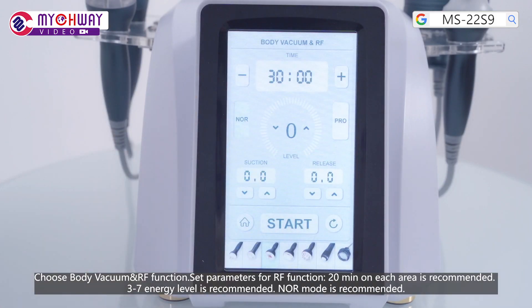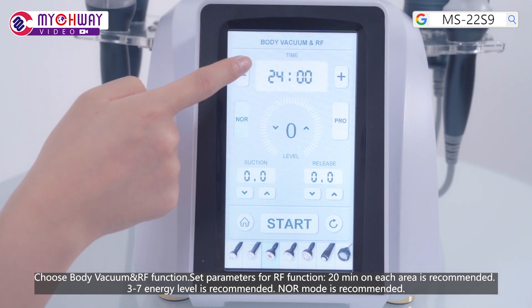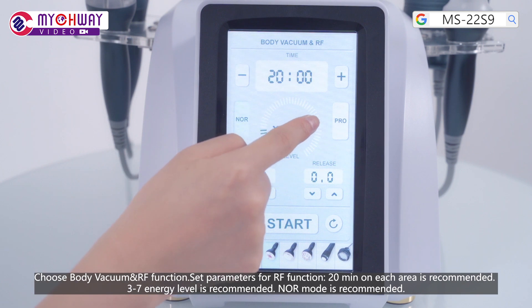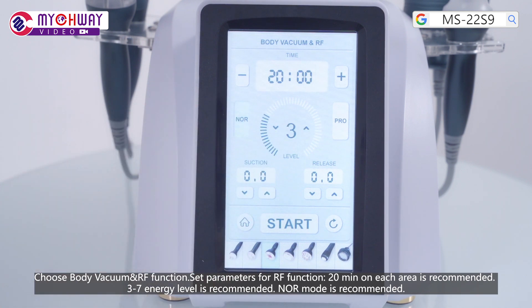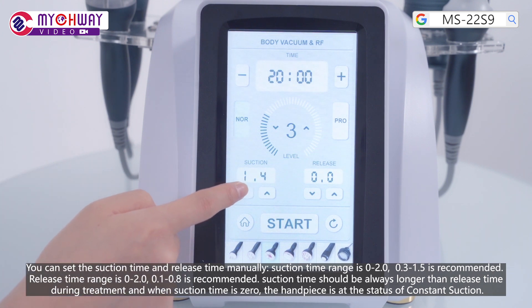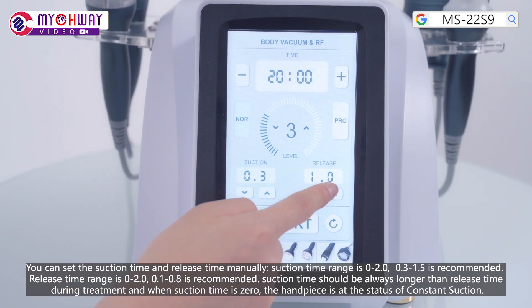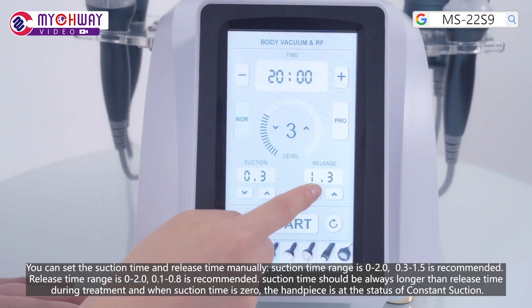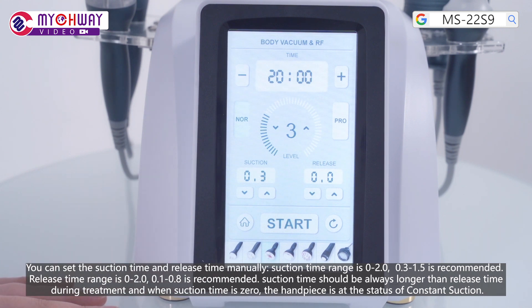Choose the body vacuum and RF function. Set parameters for the RF function: 20 minutes on each area is recommended; 3-7 energy level is recommended; NOR mode is recommended. You can set the suction time and release time manually. Suction time range is 0 to 2 seconds; 0.3 to 1.5 is recommended. Release time range is 0 to 2 seconds; 0.1 to 0.8 is recommended. Suction time should always be longer than release time during treatment. When suction time is 0, the handpiece is in constant suction mode.